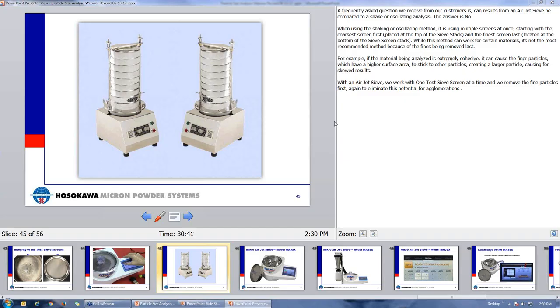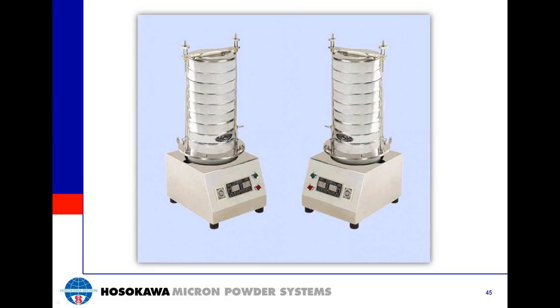A frequently asked question is: can results from the Airjet sieve be compared to a shaking or oscillating analysis? The answer is no. The shaking or oscillating method uses multiple sieve screens at once, starting with the coarsest screen on top and ending with the finest at the bottom. While this method can work for certain materials, it's not the most recommended because the fines are removed last. With the MAJS-X, we work with one test sieve screen at a time and remove the fine particles first, eliminating any potential for agglomerations or cohesion that can produce inaccurate results.